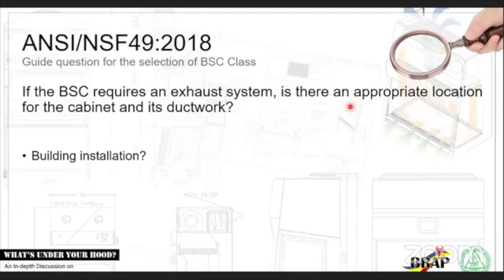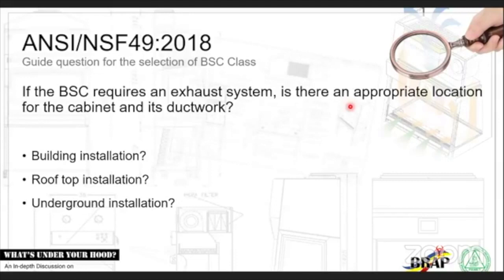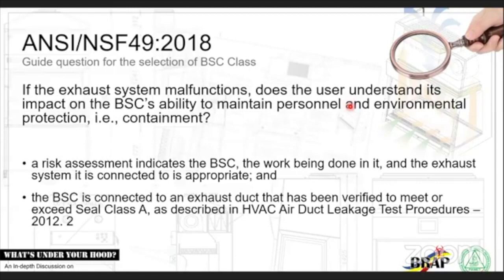Again, the ductwork. So you need to know where you want to place your biosafety cabinet. Is it in a building installation, in the middle of the building? Is it on the rooftop, which will make it easier? Or is it underground? Okay. Now, if the exhaust system malfunctions, does the user understand? Now, these are very tough ones to explain. The biosafety cabinet is connected to an exhaust duct that has been verified to meet or exceed SEAL Class A. Again, this is used basically for your Class 2 B2 cabinets and probably your Class 3 cabinets as well.